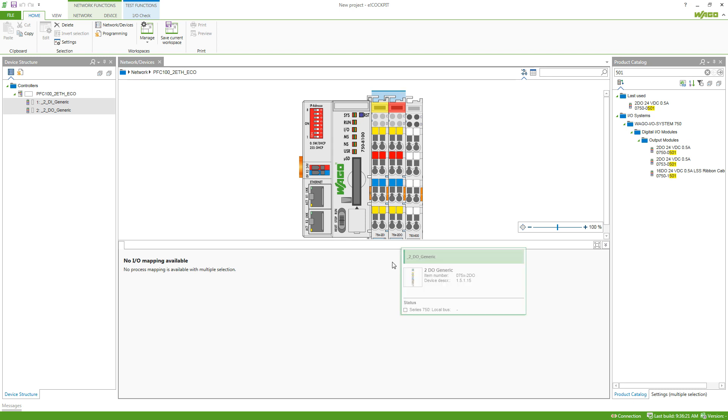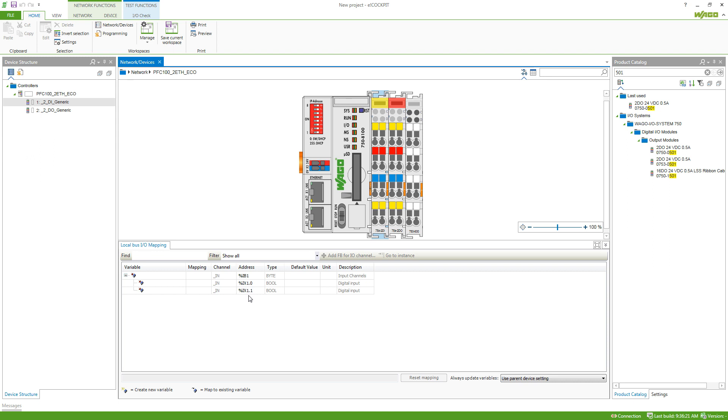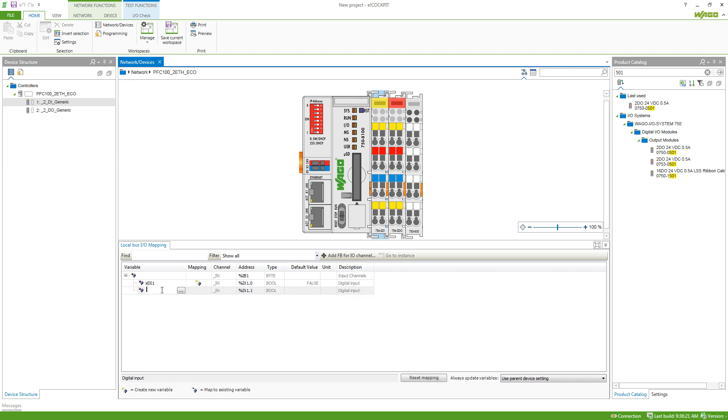Now to continue we just select a module and we need to add a mapping for a module. So I click on a little plus here we can see the two channels this module has. It already has two addresses which we could already use to be able to communicate with the module but this is not very handy because the addresses might change if you add or remove modules from your KBUS.